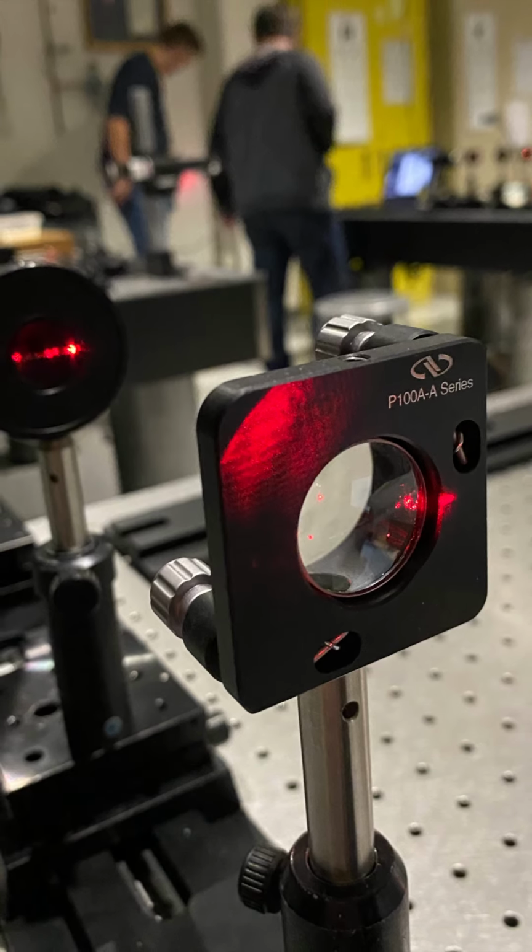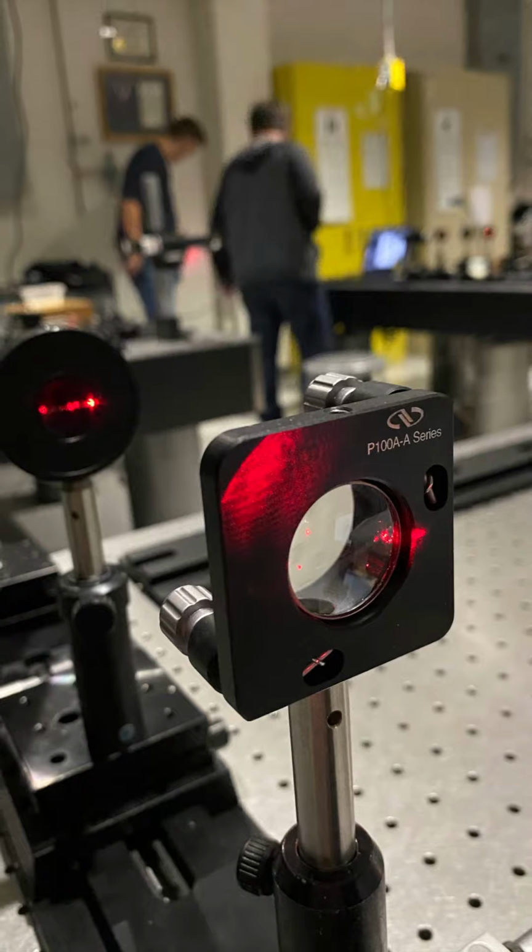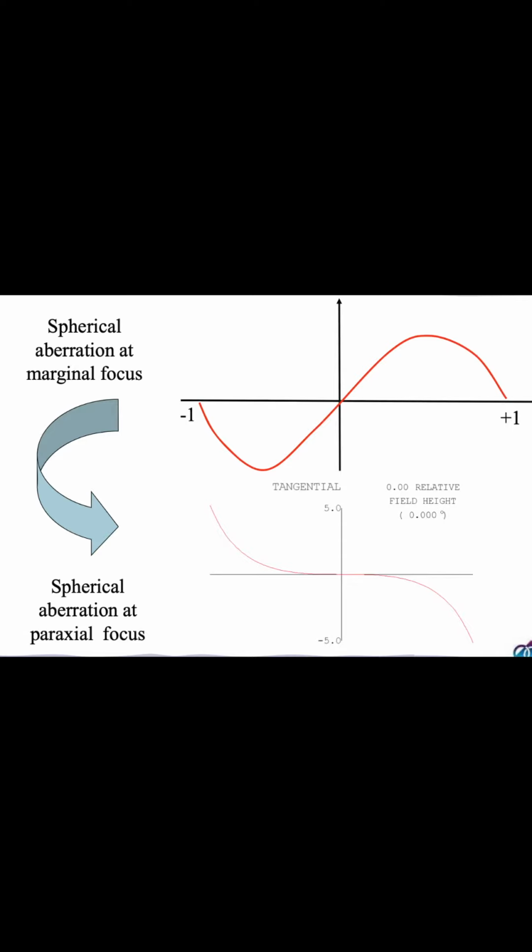The microscope was aligned to the marginal focus by passing a ray through the outermost edge of the pupil. Recall that the rays from the edge of the pupil cross the axis at the marginal focus. To ensure alignment, this was done for both extremes of the Hartmann mask. If well aligned, the difference in microscope positions would be minimal.